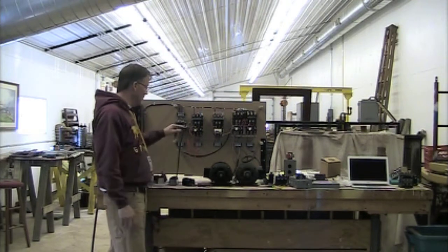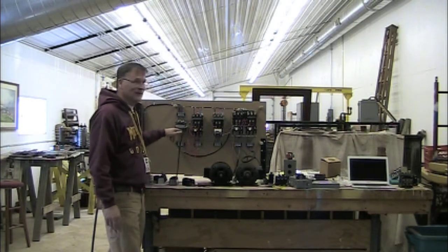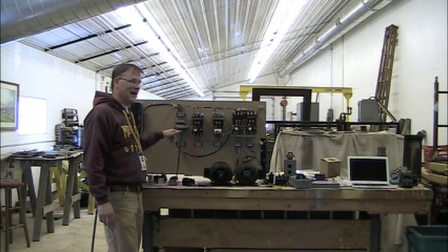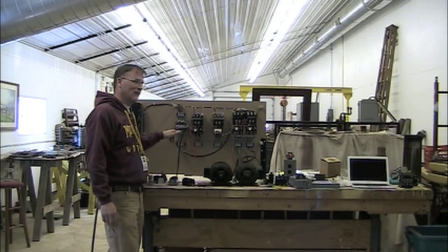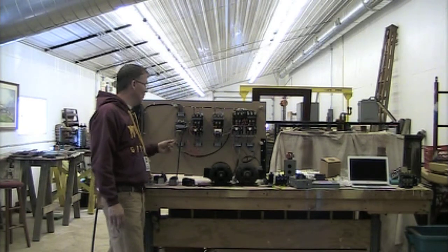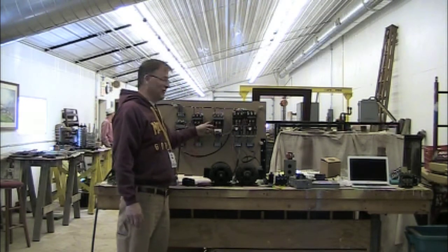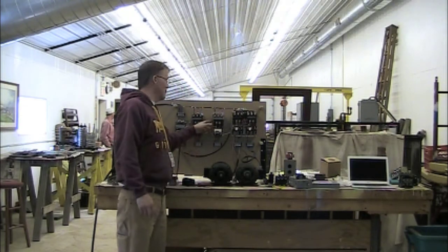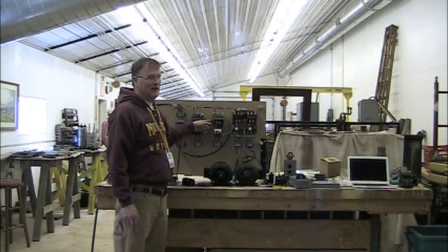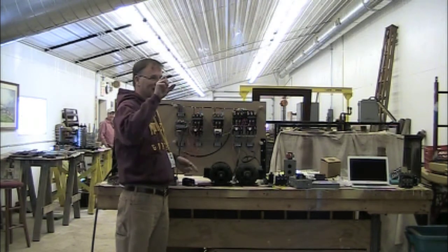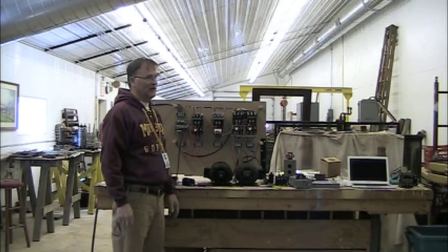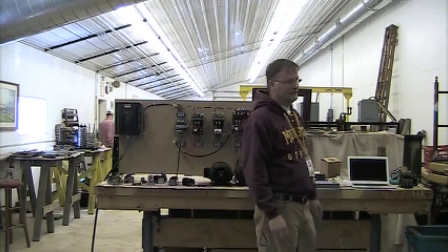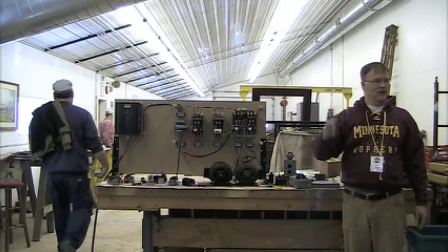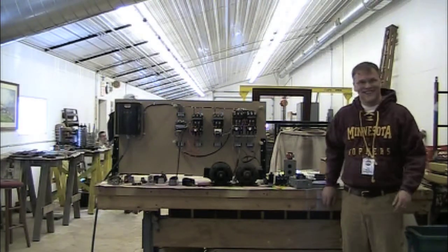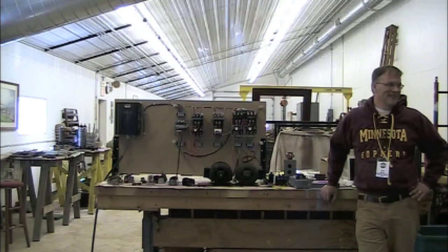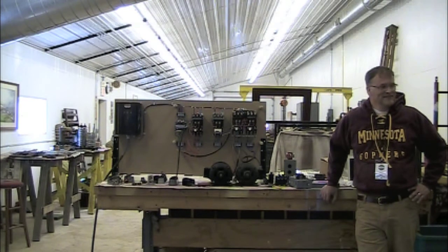And it's typical of all the Allen Bradley things. It's just a little modular fuse block that attaches right onto the control transformer and gives you the other output to it. They actually make a little one that goes on here. It's a Bulletin 595, I don't remember, but it's a control circuit fuse block that's got 2 little cartridge fuses in it, and it mounts right to the side of the starter. If you want to buy one new, they're probably $100 or something. Those aren't very common, and I've never gone looking for them.